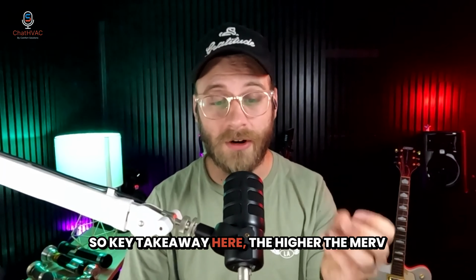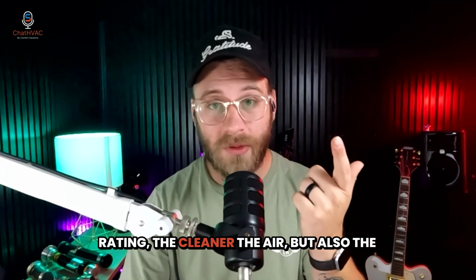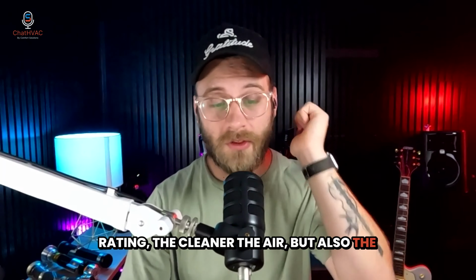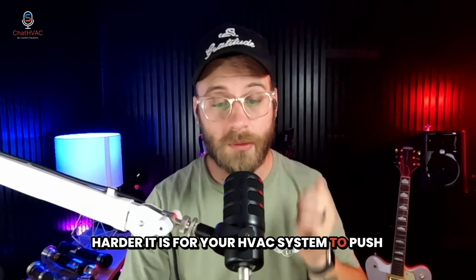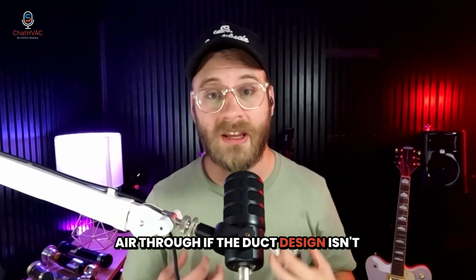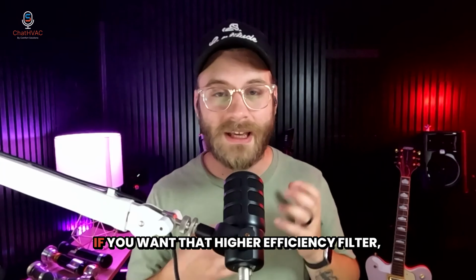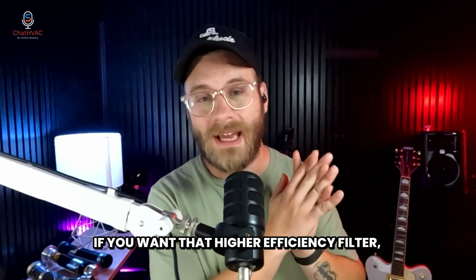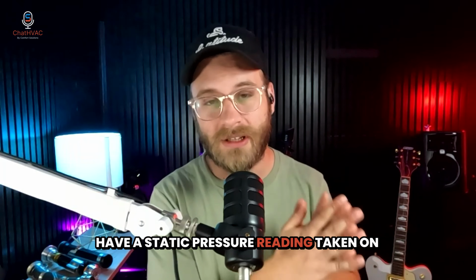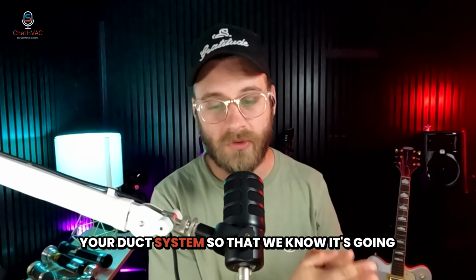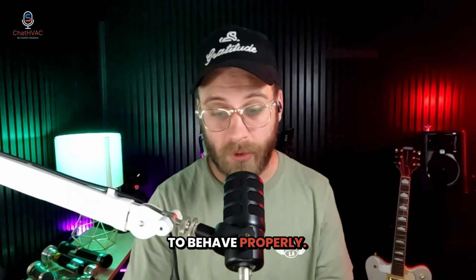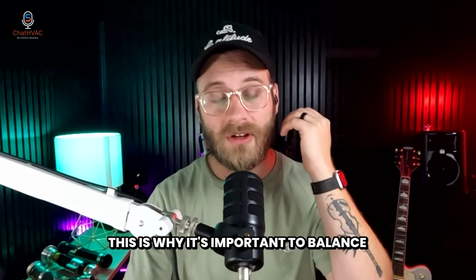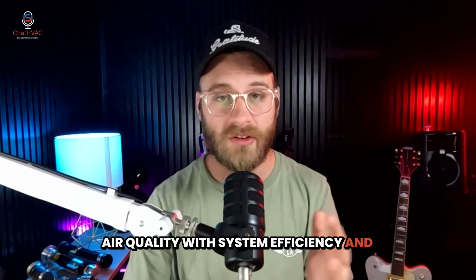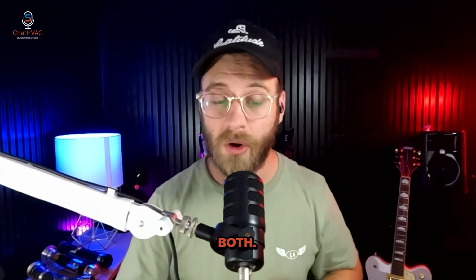So key takeaway here, the higher the MERV rating, the cleaner the air, but also the harder it is for your HVAC system to push air through if the duct design isn't proper. If you want that higher efficiency filter, have a static pressure reading taken on your duct system so that we know it's going to behave properly. This is why it's important to balance air quality with system efficiency. But you can have both.